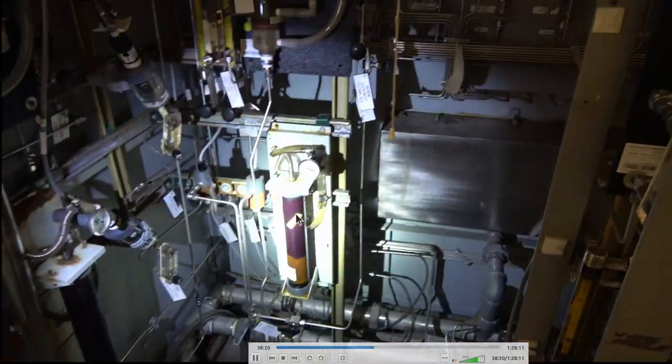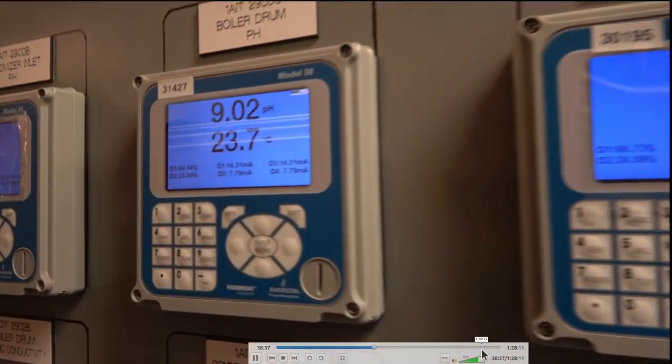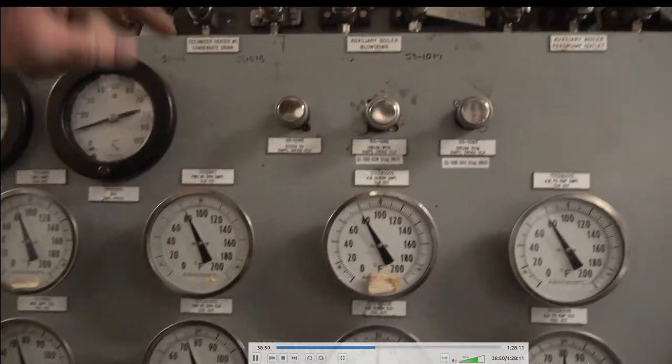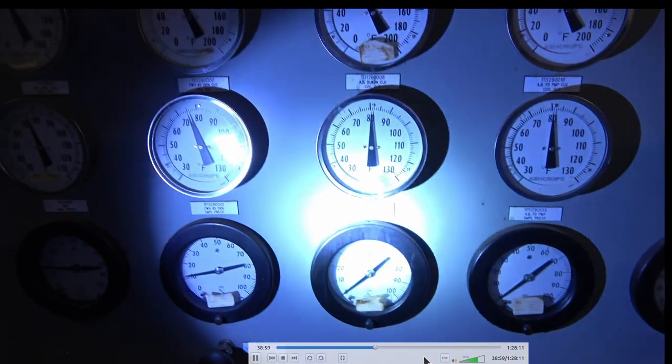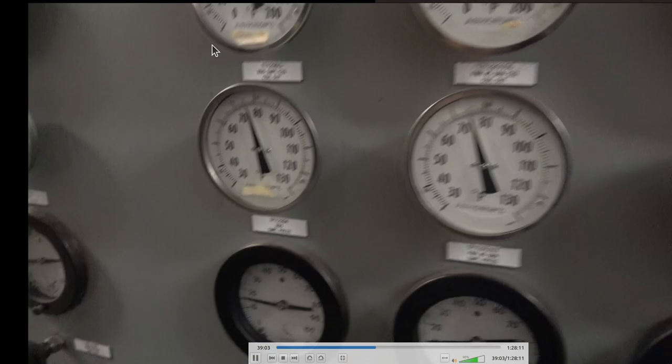That way you get an accurate pH. Back here you have cation columns for getting the cation conductivity — you can see the color change: the yellow is exhausted, the purple is still good. That's where you do conductivities. There are instruments for dissolved oxygen and sodium. You have 2,400 psi coming down here — you have to drop the pressure down so you can run the samples on it. The sample temperature is pretty critical. A filtered water tank feeds the chemistry lab where analysis is run on everything.